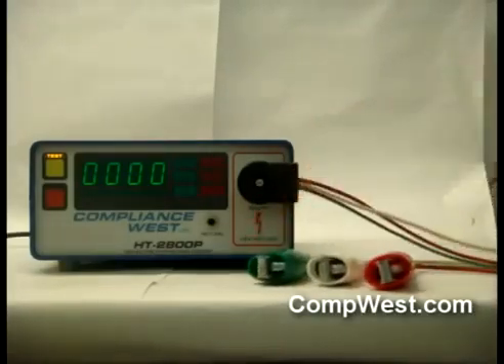Next, set all the switches and breakers in the home to the on position. Arc fault breakers and smoke detectors should be removed before testing.